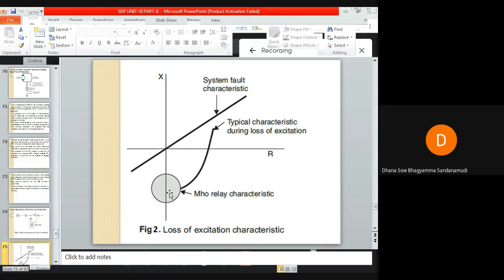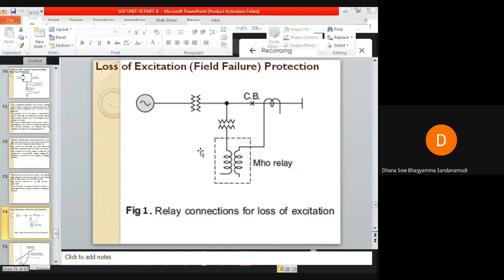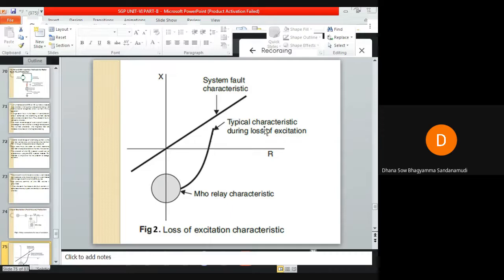Now, under normal operating condition, when the synchronous generator is connected to the grid, it supplies lagging reactive power to the grid. It supplies active power as well as reactive power, and the power factor is lagging. The impedance of the alternator is seen in the first quadrant of the RX diagram, so under normal operating condition, the characteristics will lie in the first quadrant.